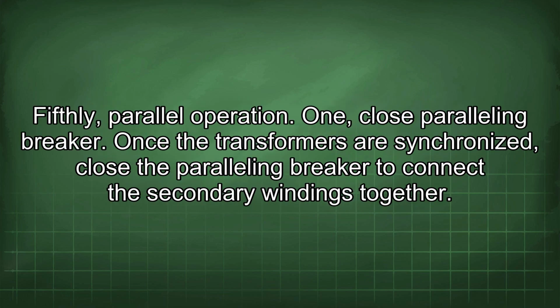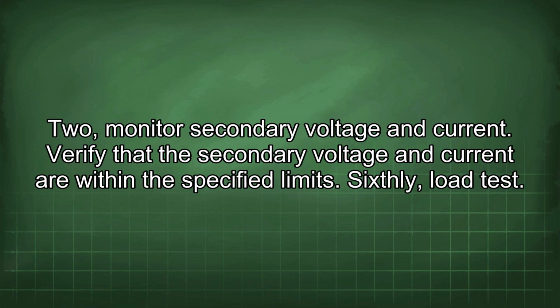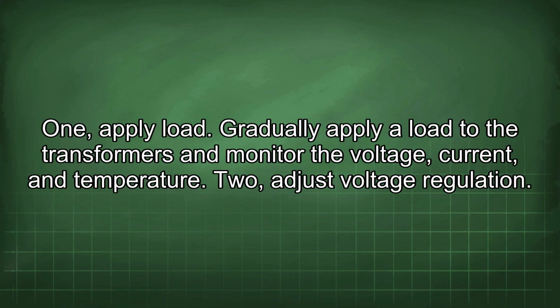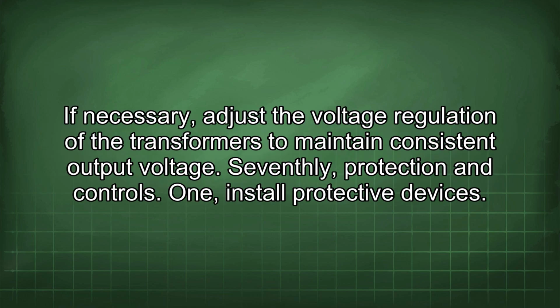Fifthly, parallel operation. 1. Close paralleling breaker. Once the transformers are synchronized, close the paralleling breaker to connect the secondary windings together. 2. Monitor secondary voltage and current. Verify that the secondary voltage and current are within the specified limits. Sixthly, load test. 1. Apply load. Gradually apply a load to the transformers and monitor the voltage, current, and temperature. 2. Adjust voltage regulation. If necessary, adjust the voltage regulation of the transformers to maintain consistent output voltage.